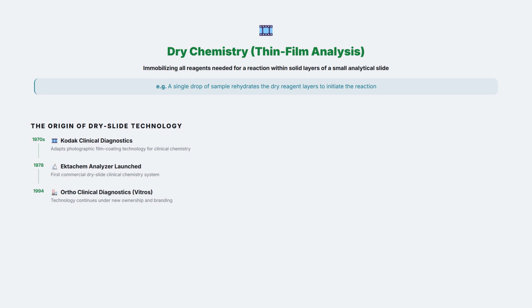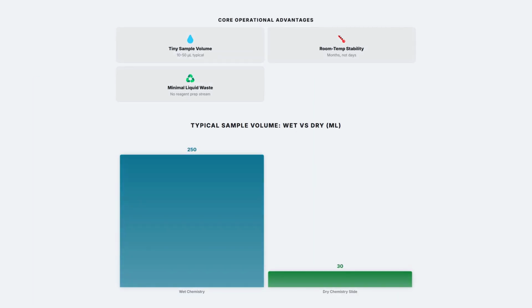reaction within solid layers of a small analytical element. The technology traces back to Eastman Kodak's Clinical Diagnostics division, which commercialized the first Ektachem analyzer in the late 1970s, adapting photographic film coating technology directly from Kodak's core business. The operational advantages that drove adoption are concrete, not marketing language. Dramatically smaller sample volumes, often just 10 to 50 microliters versus hundreds required by wet methods, room temperature reagent stability measured in months rather than days, and functionally zero liquid reagent waste stream to manage.